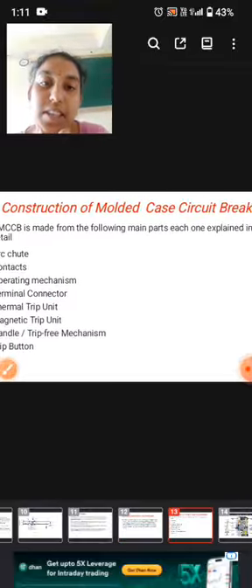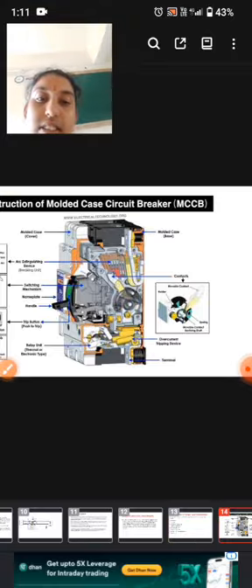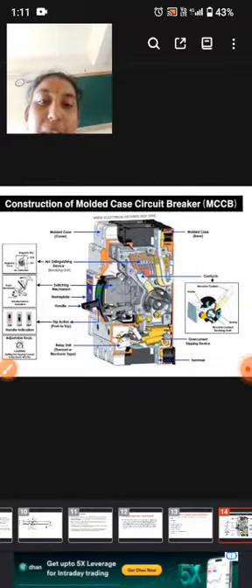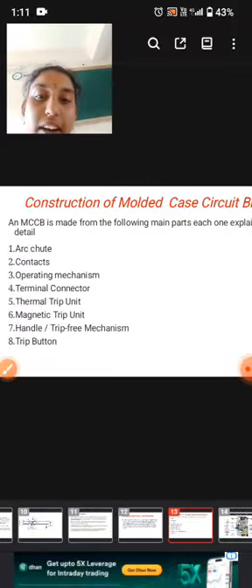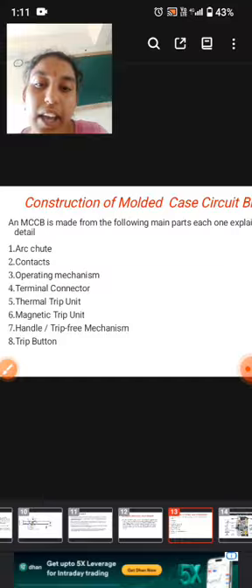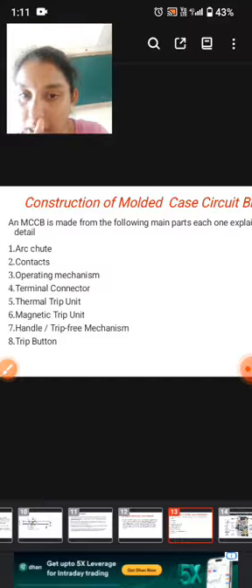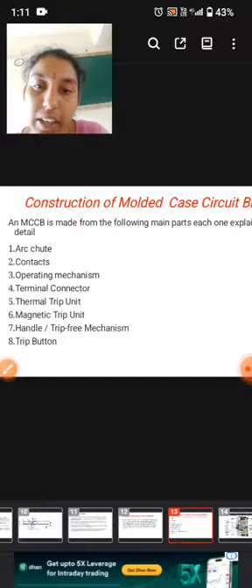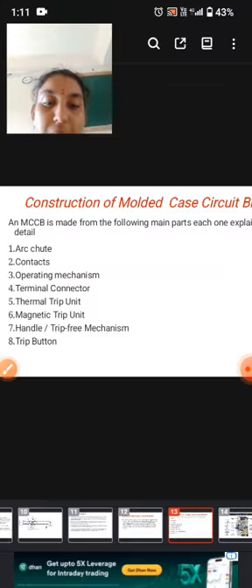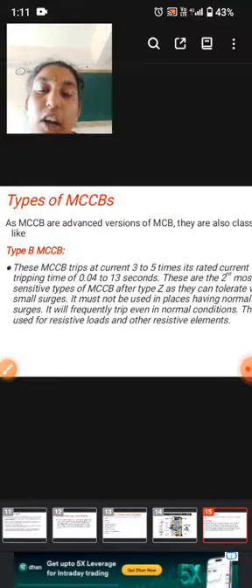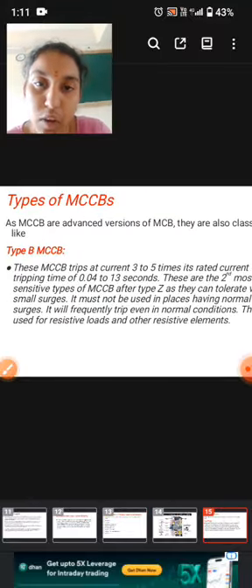Construction of MCCB. This is the construction of MCCB, and the parts of an MCCB are: arc chute, contacts, operating mechanism, terminal connector, thermal trip unit, magnetic trip unit, handle or trip free mechanism, and trip button.